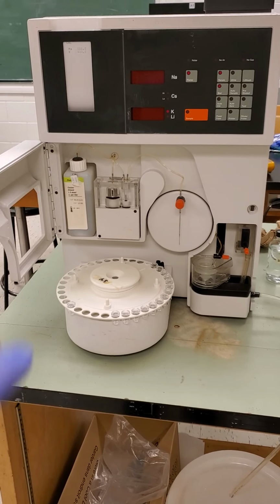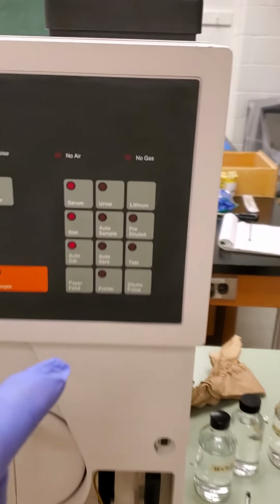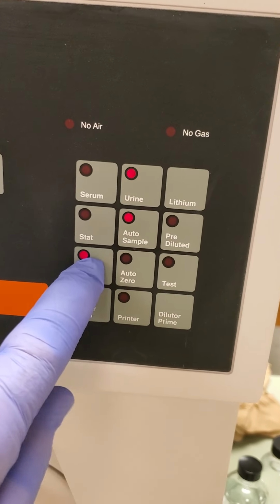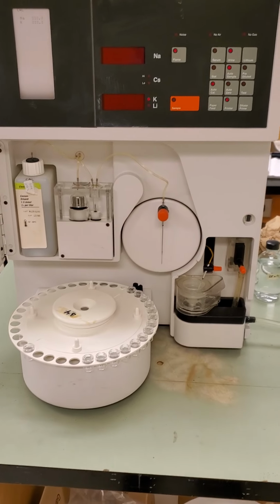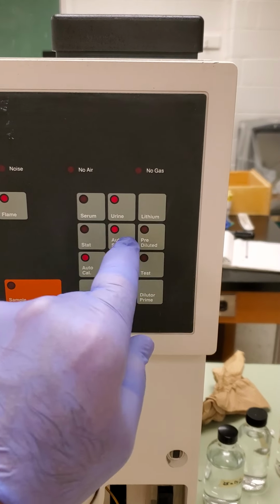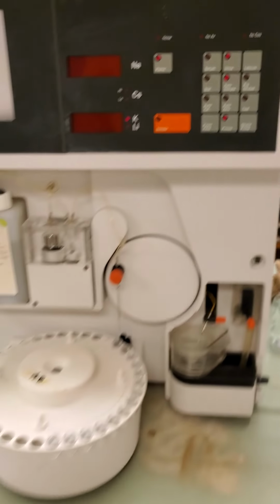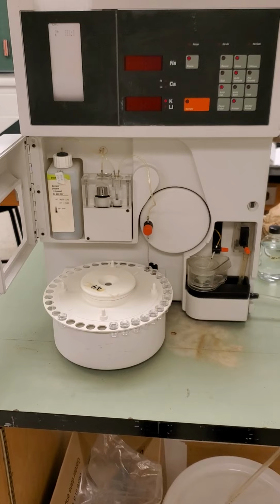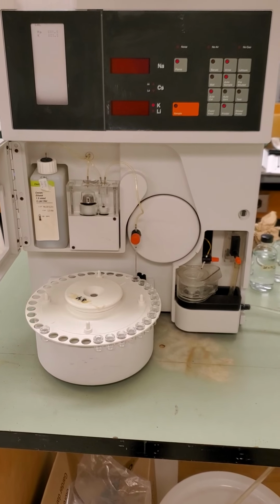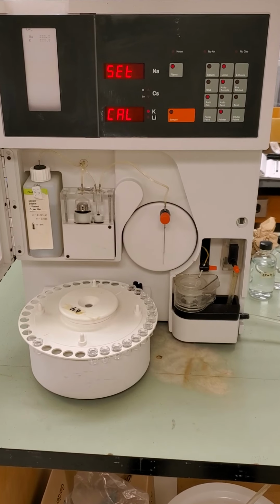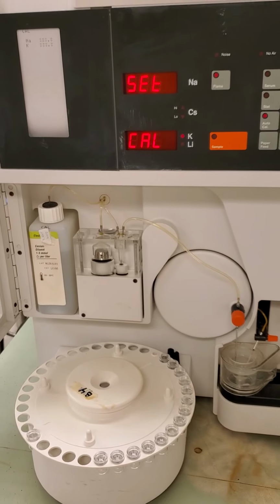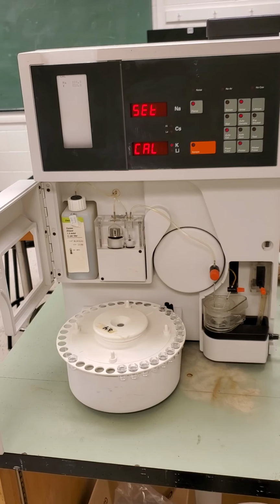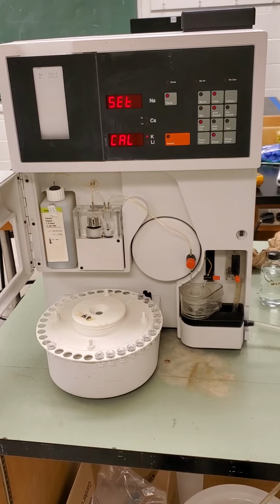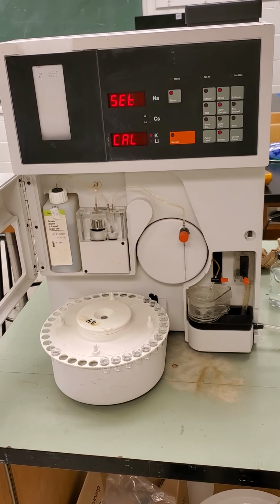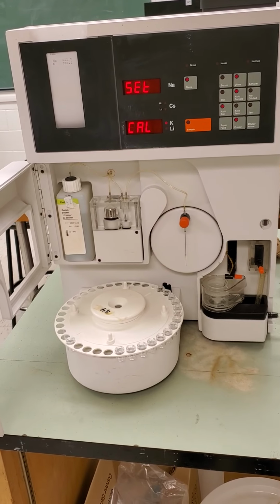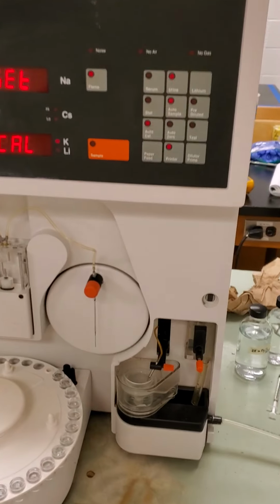Okay, so now the busy signal has gone down. So what we can do is we can select urine, auto sample, auto cal. Printer. Urine, auto sample, printer, auto cal. And then the machine starts up. It takes a calibration amount, which is 100 millimoles of sodium and 100 millimoles of potassium, and feeds it into the mixing chamber, mixes.